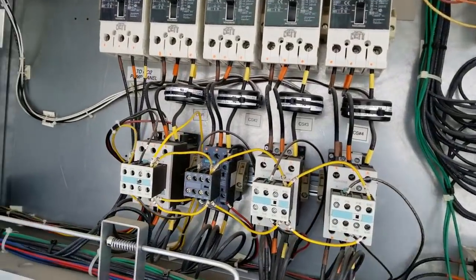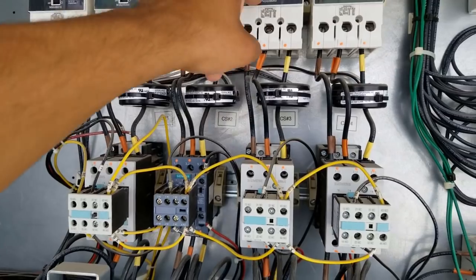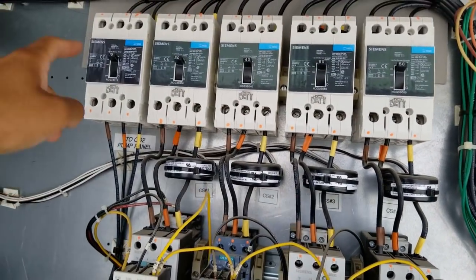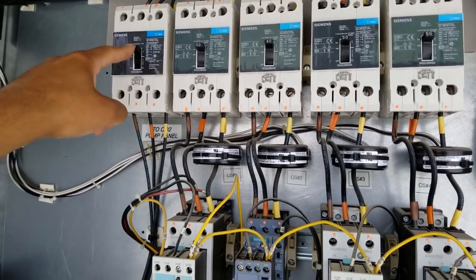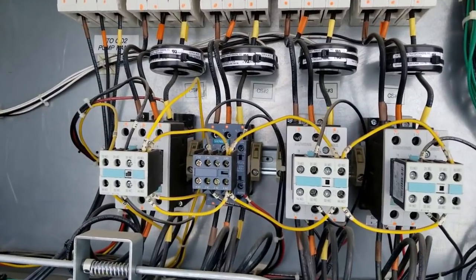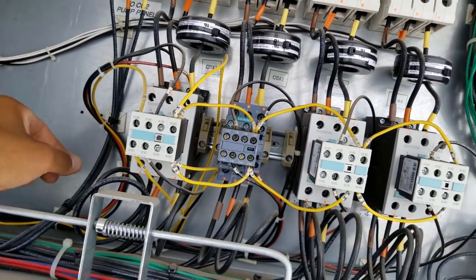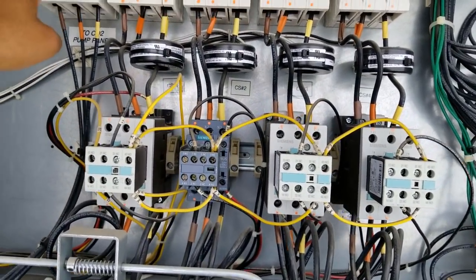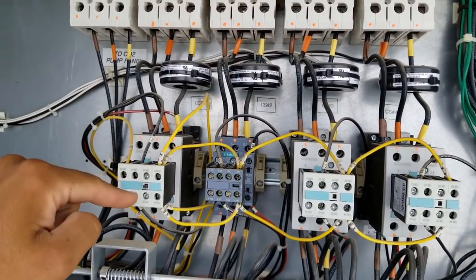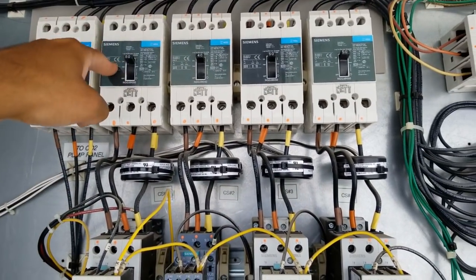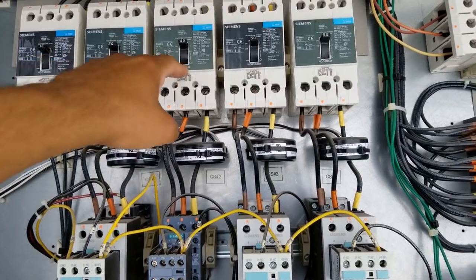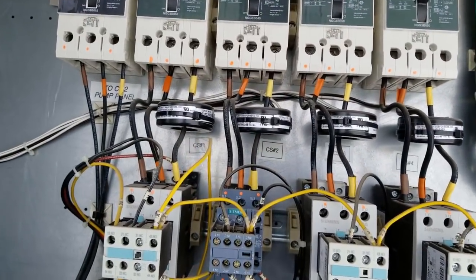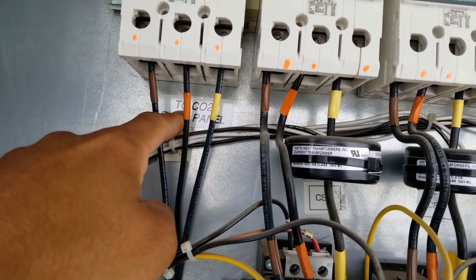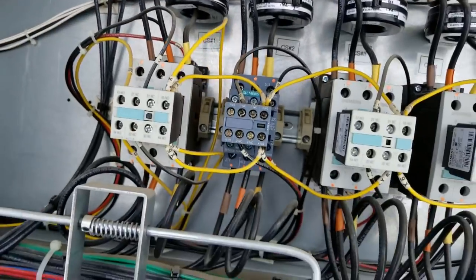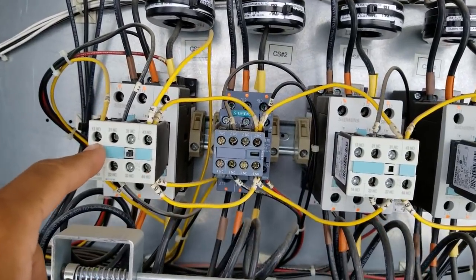Here you got your breakers to each compressor in a whole separate panel. So this is the one that's not tripped, so I was just checking to make sure it wasn't tripped. This is my contactor. Actually, my bad. This is not my breaker. This is my breaker. This is my contactor right here. So this is my breaker for compressor 1, 2, 3, 4. And then this is to power to my CO2 panel. So my contactor is not pulled in.